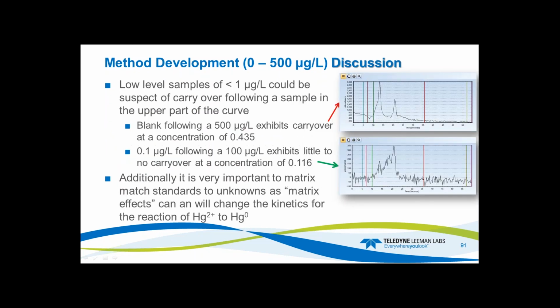Okay, so in discussion for this part, don't go below 1. A blank following a 500 might exhibit a little bit of carryover because that one blank came in at 0.453. I might be able to compensate for this by adjusting my rinse speed, rate, and/or concentration of my acids. The 0.1 after the 100 exhibited little to no carryover, and the concentration came in at 0.116, which is pretty good. And again, matrix match is very important.